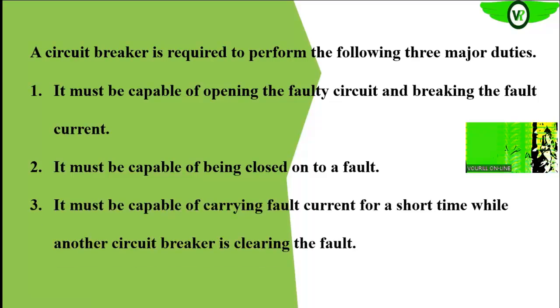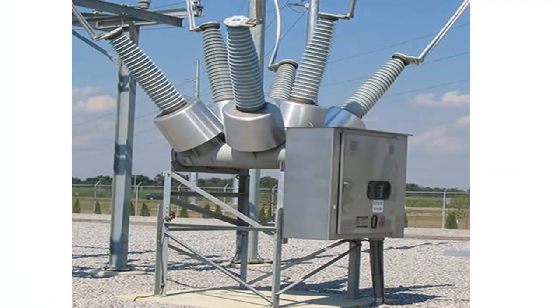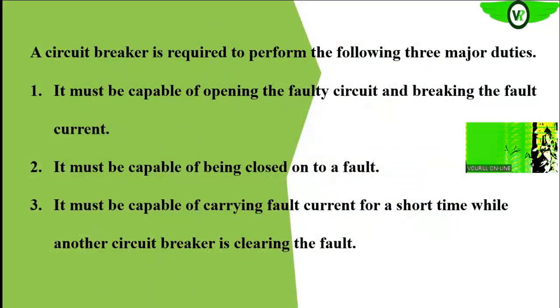Finally, the circuit breaker must be able to carry the fault current for a short time. This will allow other circuit breakers downstream to clear the fault before the upstream circuit breaker trips. If a particular circuit breaker is feeding other circuit breakers that feed other loads, we require the arrangement to trip closest to the fault. The upstream circuit breaker should have a short time delay to allow downstream circuit breakers to trip first.